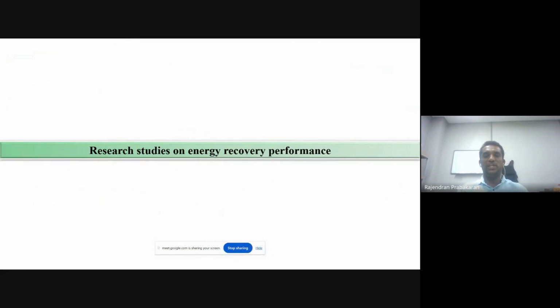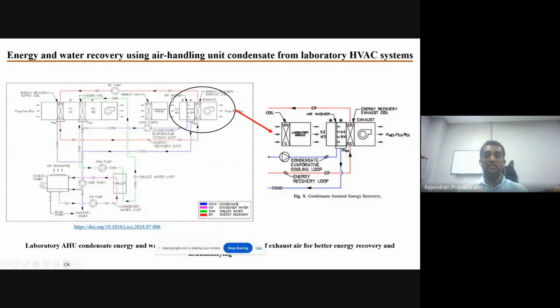Some research studies on the energy recovery performance. As I told, in this study you can see this figure, which is an elaborated one. The condensate collection was used for two purposes. As you can see from this diagram, this condensate recovery is used for pre-cooling the exhaust air and also the supply air. The same condensate water can also be supplied to the cooling towers. During cooling tower operation there are always evaporation losses, so there should always be a standby water supply. From that point of view also, we can use this condensate water in the cooling tower and reduce the external water source consumption.